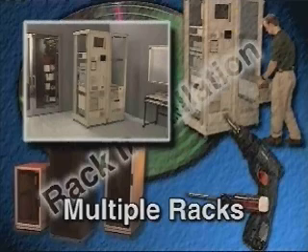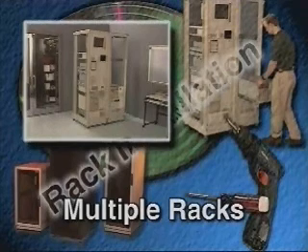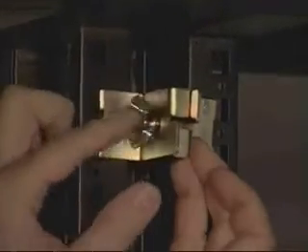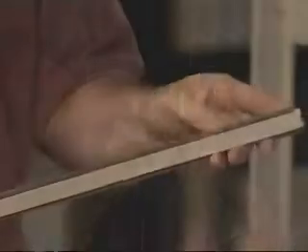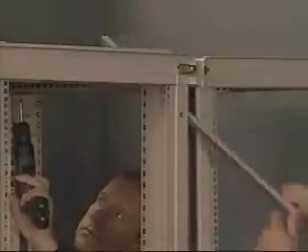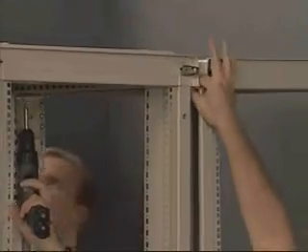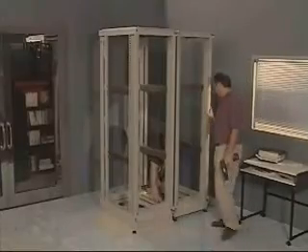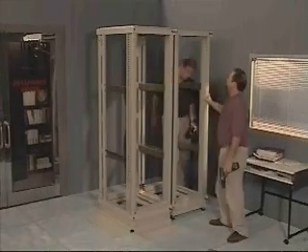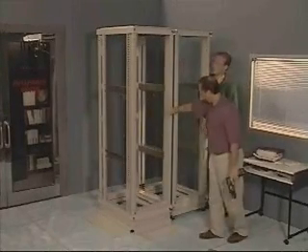Multiple racks need to be joined or coupled to save space and offer stability. Once coupled, stabilizing feet are not required. Coupling kits for the rack 7142 provide insulated dust strips to cover top and bottom spaces between the racks and the cosmetic faceplates that hide the gaps. These kits are ordered separately and allow you to join rack 7142 units into a suite using the four angle brackets provided with the kit.